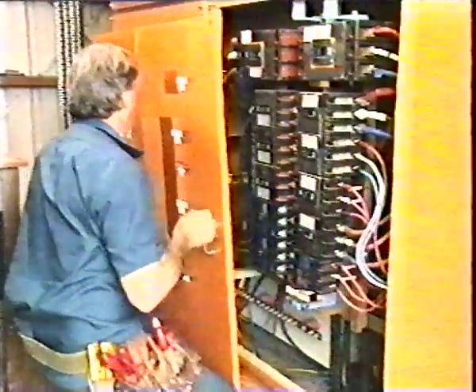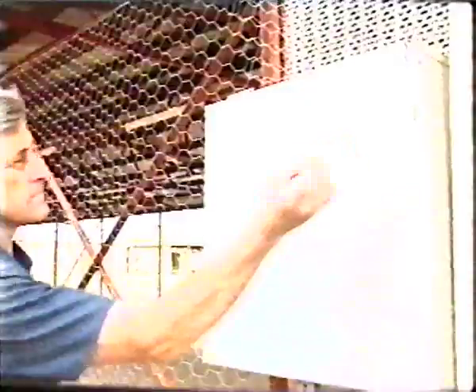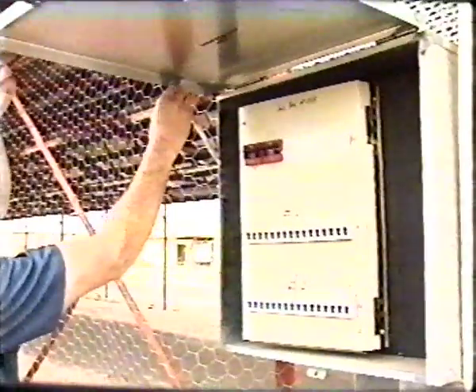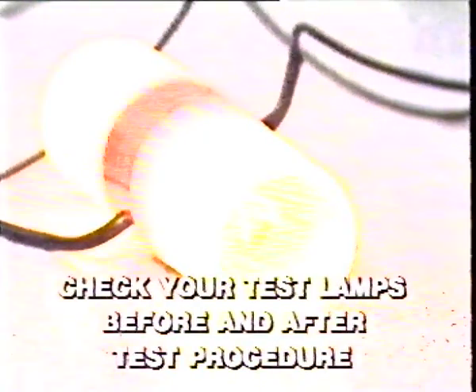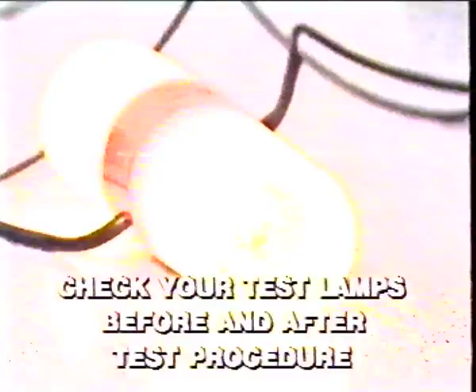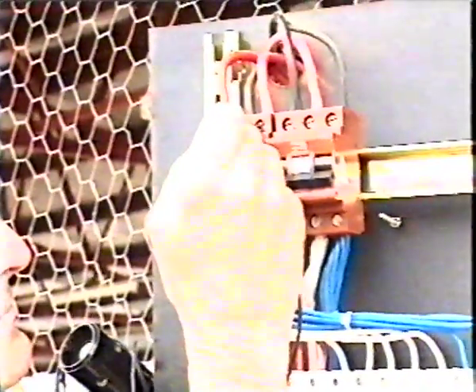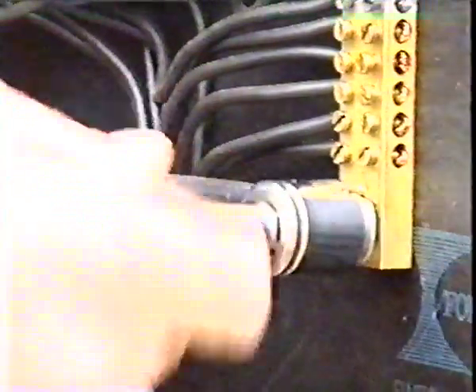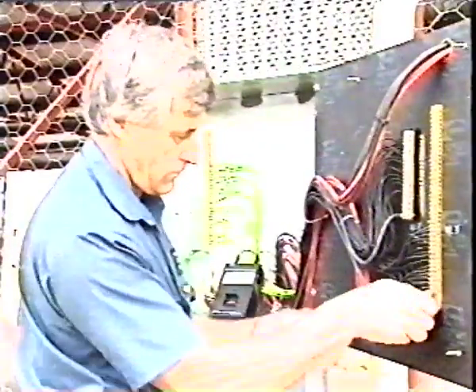Disconnect supply at the origin of the submains, usually by opening the protective devices at the supply switchboard. Prove that the exposed metal enclosure of the distribution board is dead with a neon test probe. Disconnect the outgoing circuit active conductors, usually by opening the protective devices. Before testing, check that your test lamps are in operating condition. When the test is complete, check your test lamps again. Prove that the live parts of the distribution board are dead with test lamps from active to neutral and active to earth. Disconnect the submain neutral conductor from the distribution board neutral link.